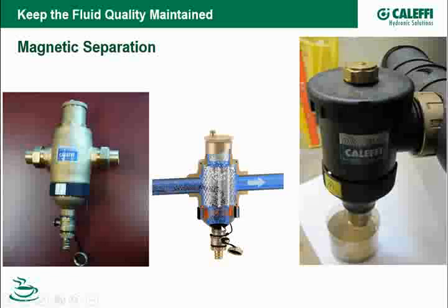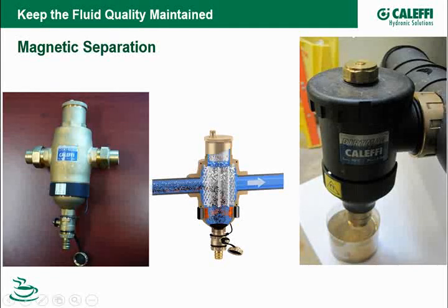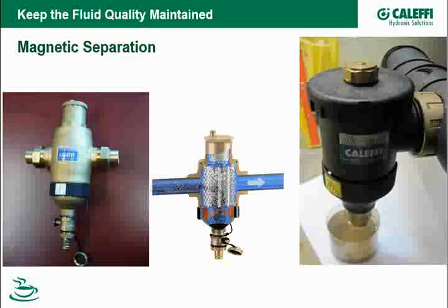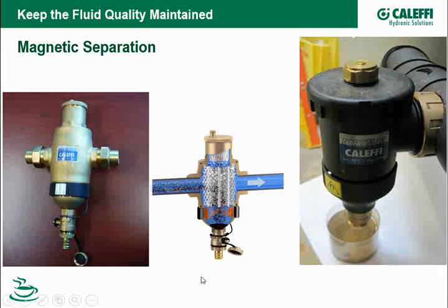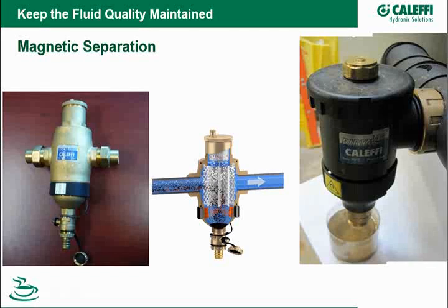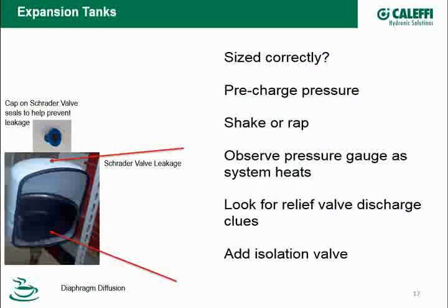Most of the time it'll present itself as pinholes in the expansion tank, but it can be also eating away in your pump volutes, or if you've got a cast iron boiler or any ferrous components, it'll start eating away on that. And there's an example. This is one I've got on my wood boiler at home, and every year I just take a little glass or plastic cup on there, blow it down, and see what kind of particles are coming out of it. So shop around for a good magnetic protection device next system.